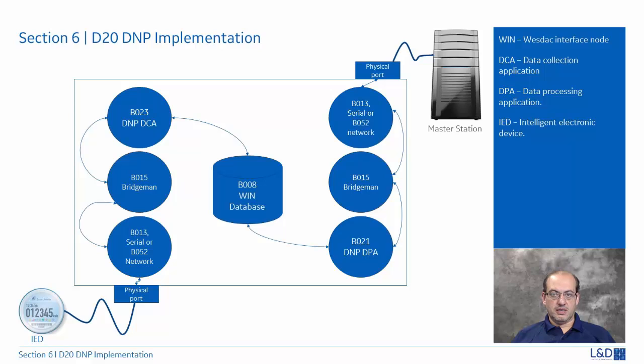The remote terminal unit has the application architecture that will allow the storage of information until requested by the master station. Okay, so let's start the journey of information or data via DNP protocol from the IED all the way to the master. When an event takes place in the field, it's recorded by the IED, and that data change or event will be formulated in a DNP message based on the DNP standard, and then transmitted to the physical port connected to the IED.